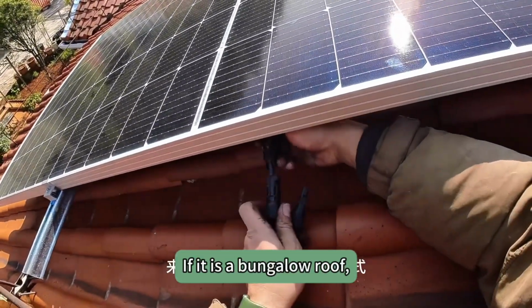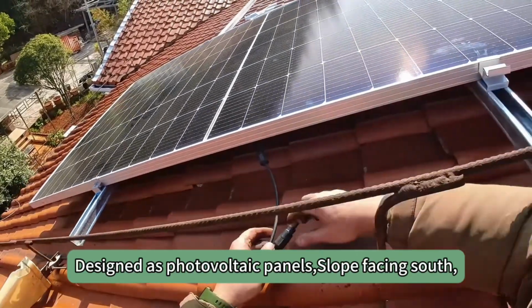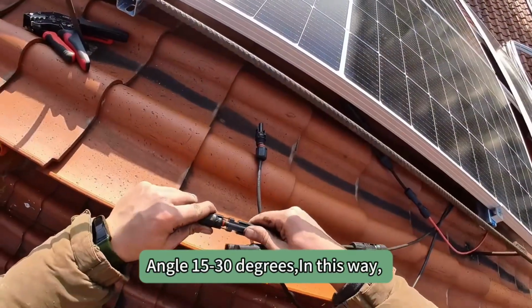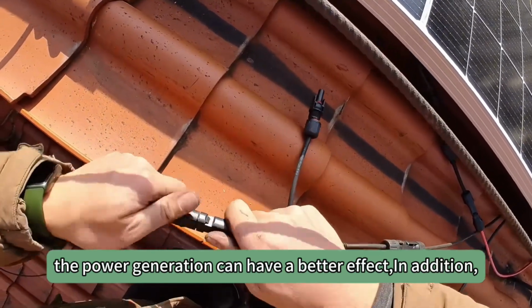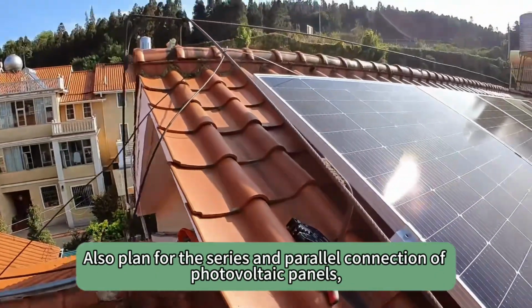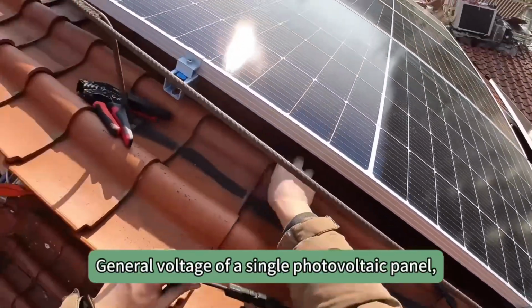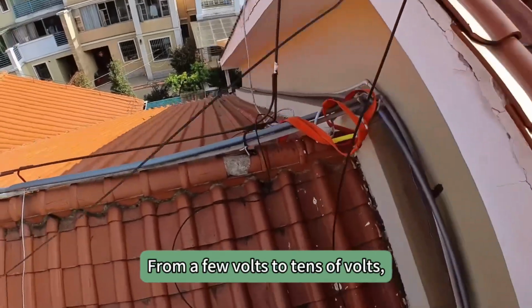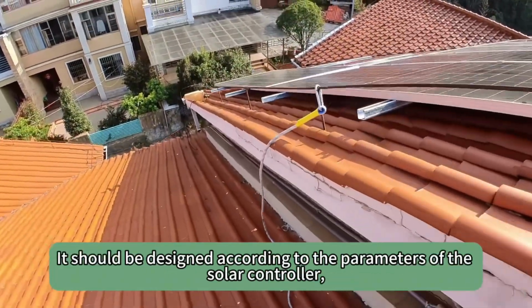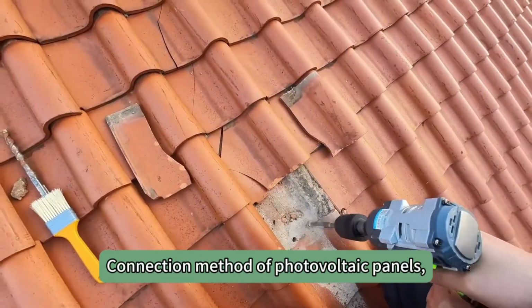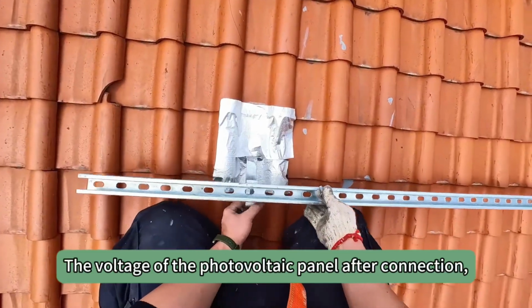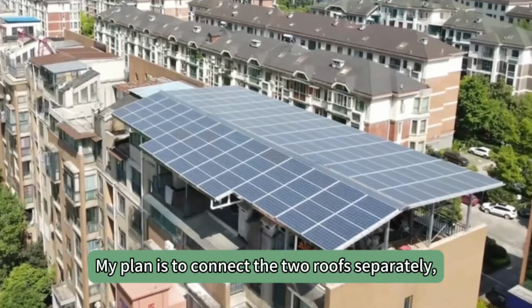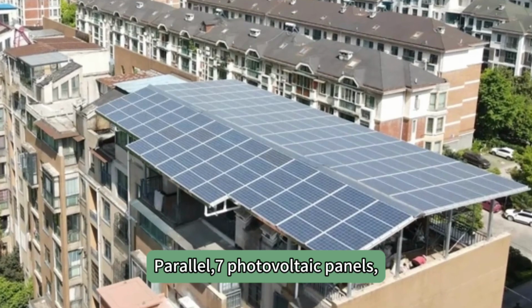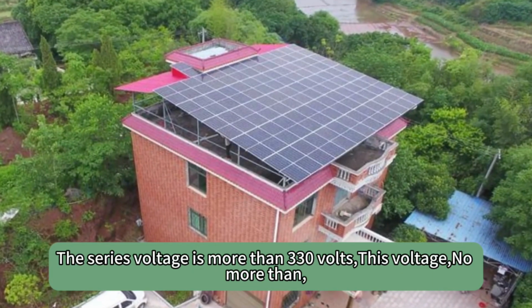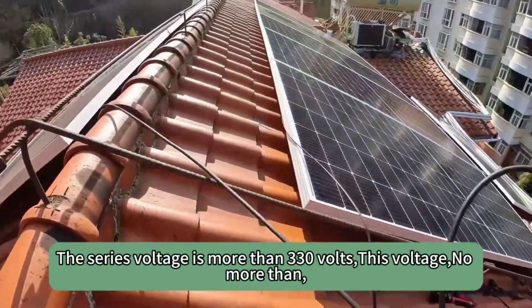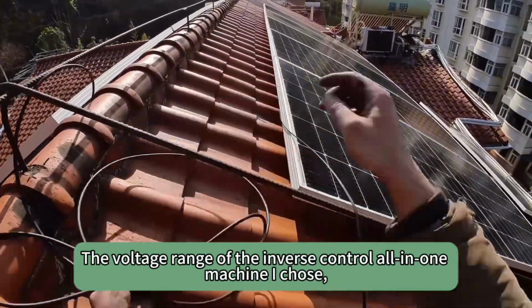If it is a bungalow roof, design the photovoltaic panels with the slope facing south at an angle of 15 to 30 degrees, and the power generation can have a better effect. In addition, plan the series and parallel connection of the photovoltaic panels. The voltage of a single photovoltaic panel is generally from a few volts to tens of volts. The connection method should be designed according to the parameters of the solar controller, and the voltage of the panels after connection must not exceed the tolerance range of the controller. My plan is to connect the two roofs separately in parallel, with a series voltage of more than 330 volts. This voltage does not exceed the voltage range of the inverter-controller all-in-one machine I chose.